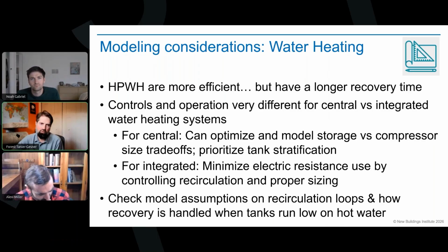Yeah, I mean, I guess just to put a finer point on that, typically with these systems, the recirculation is handled with a swing tank, which is electric resistance. So to Alexi's point, in the impact of demand, not accounting for that can overestimate the value of the heat pump and underestimate the potential peak contribution from your domestic water system. And so, knowing how your recirculation loop is, knowing strategies to reduce the load of your recirculation losses through insulation and more optimized recirc loops is really important to capturing the full picture of how your hot water system is impacting your building demand. Yep.